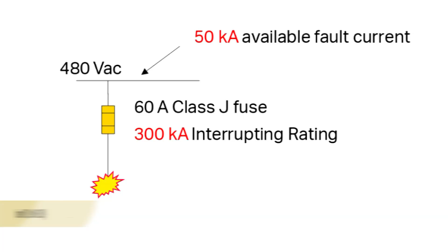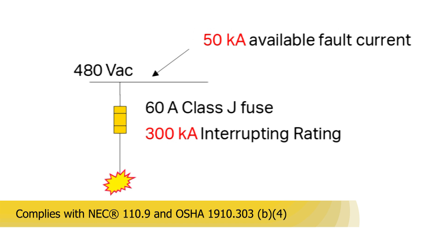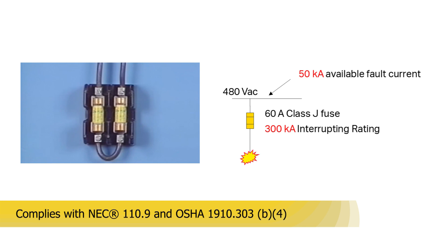The final test is not as exciting, but it is very important to demonstrate the proper application of overcurrent protective devices when it pertains to interrupting fault current. Again, the test circuit is the same, capable of delivering 50,000 amps of fault current, but in this case, the fuses protecting the circuit are Bussmann series Low-Peak dual element, time delay LPJ fuses with a 300,000 amp interrupting rating. Notice how the fault was cleared safely and without violence.